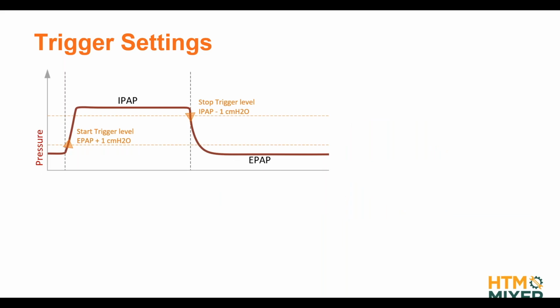In BiPAP ventilation, our upper pressure limit is called IPAP and our lower pressure limit is called EPAP. And typically we would then set the trigger level for the start trigger at the level of EPAP plus 1 centimeter of water, and a stop trigger on the falling edge at IPAP minus 1 centimeter of water. And that would work perfectly fine.